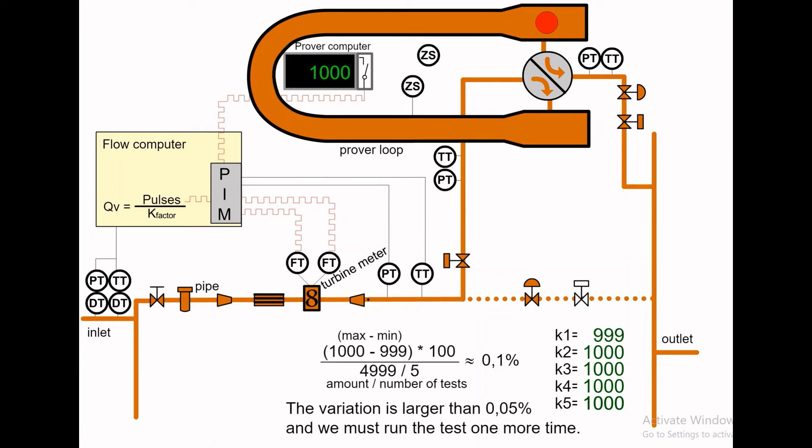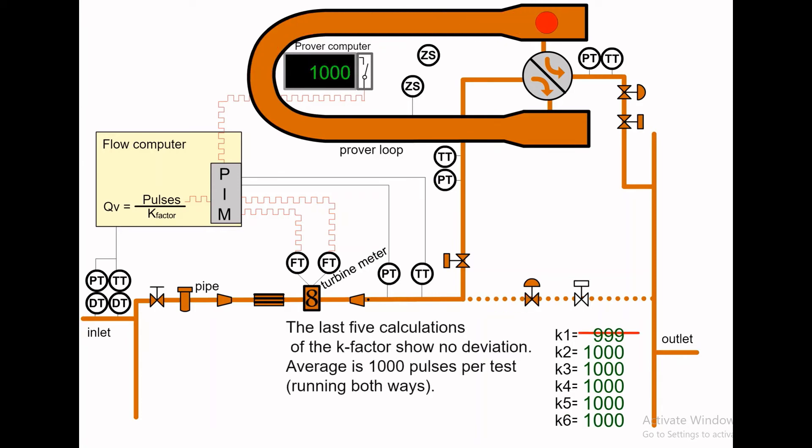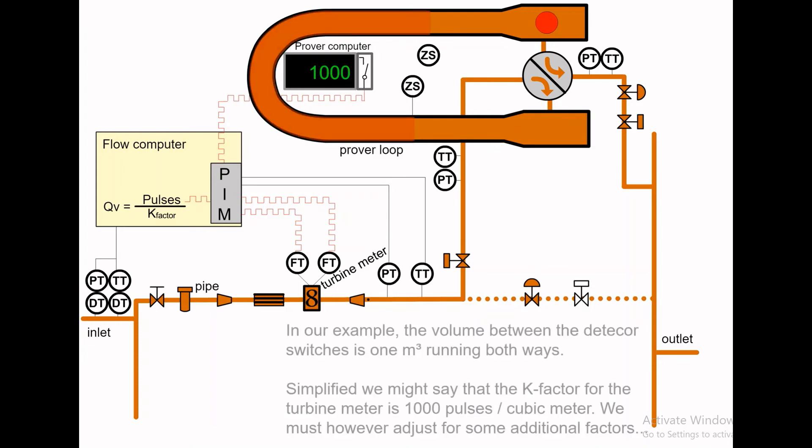The variation is larger than 0.05% and we must run the test one more time. The last five calculations of the k-factor show no deviation. The average is 1000 pulses per test, running both ways. In our example, the volume between the detector switches is one cubic meter running both ways. Simplified, we might say that the k-factor for the turbine meter is 1000 pulses per cubic meter.